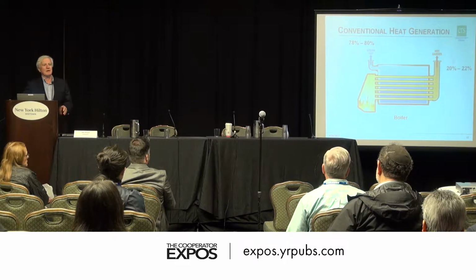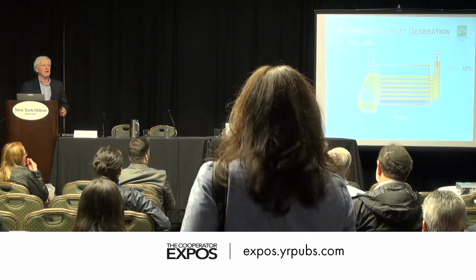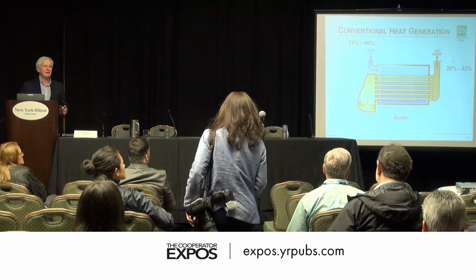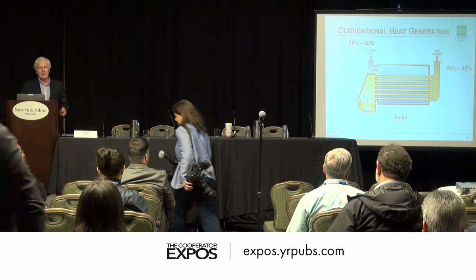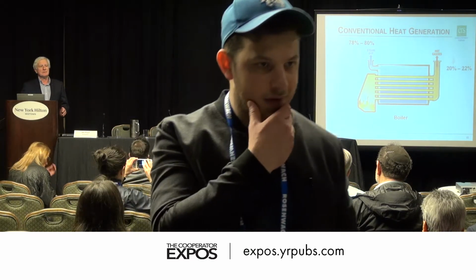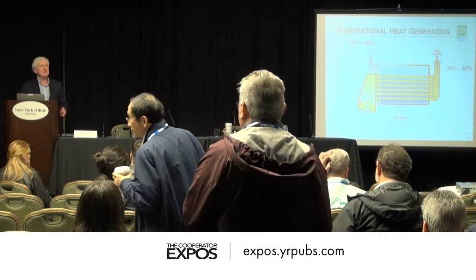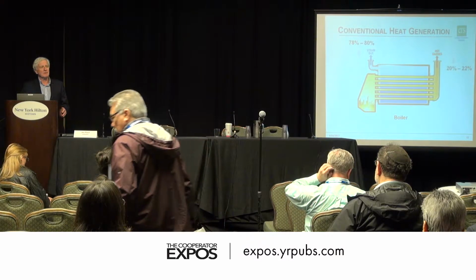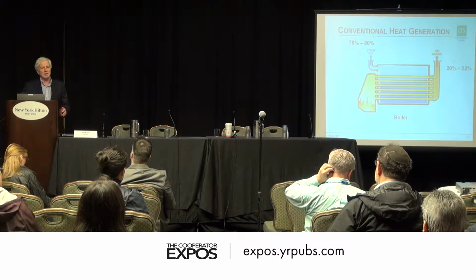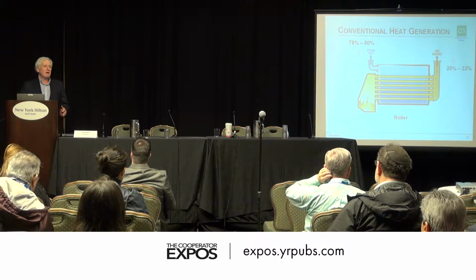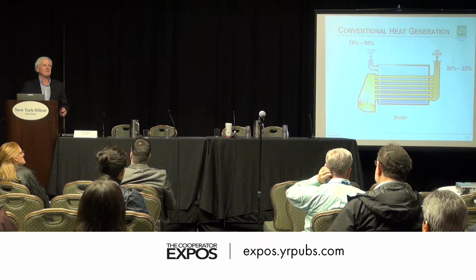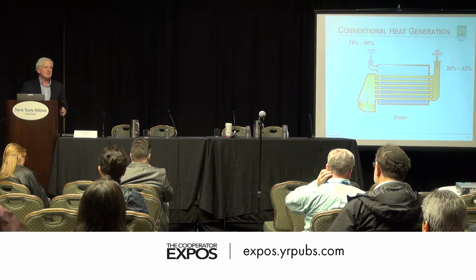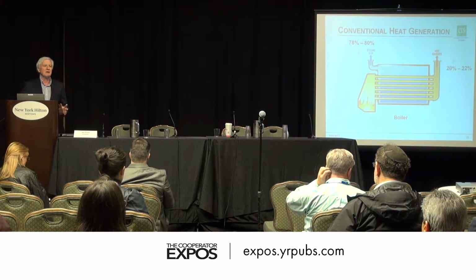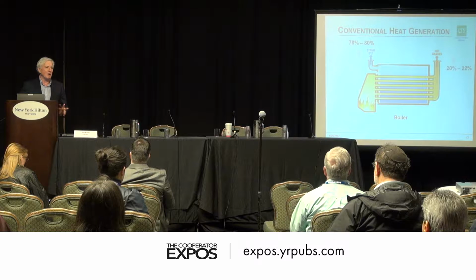You're all familiar with boilers in your building that produce domestic hot water and heat, unless you're on Con Ed steam. Typically a boiler produces steam and hot water at about 80% efficiency—a bit more efficient producing hot water, a bit less producing steam. About 20% of the fuel energy value goes up the stack. You can get a condensing boiler with efficiencies up in the 90s, but most buildings will have a boiler in the 80% range.